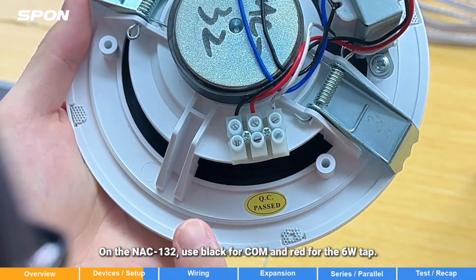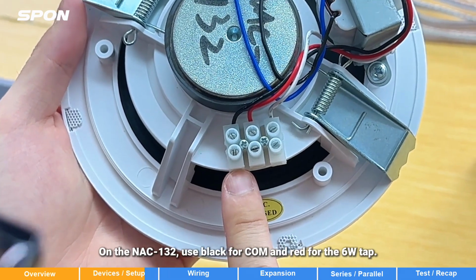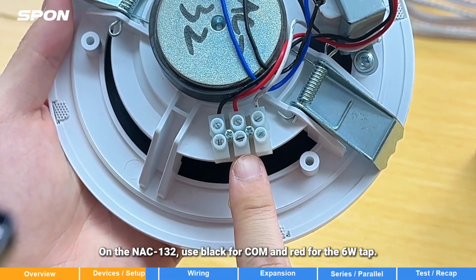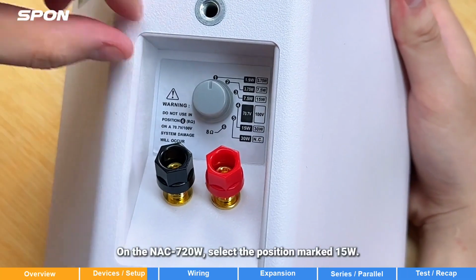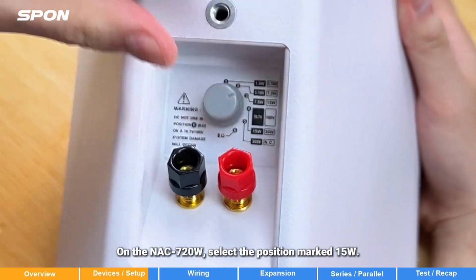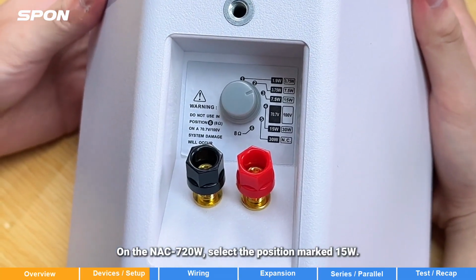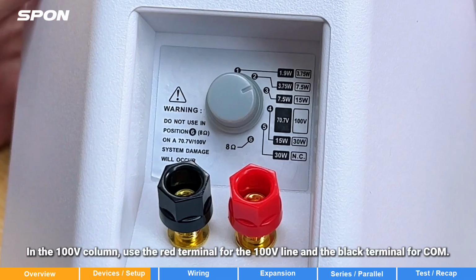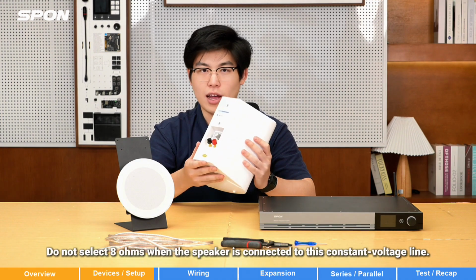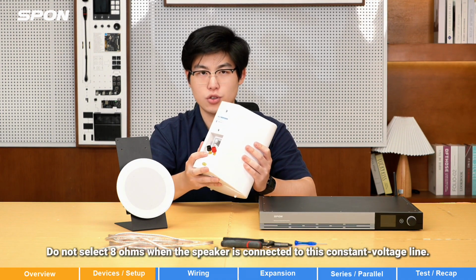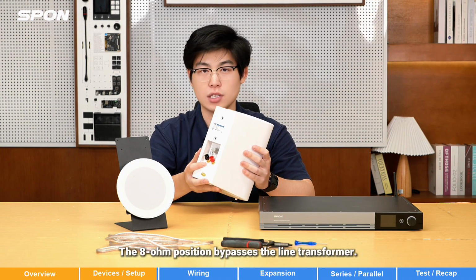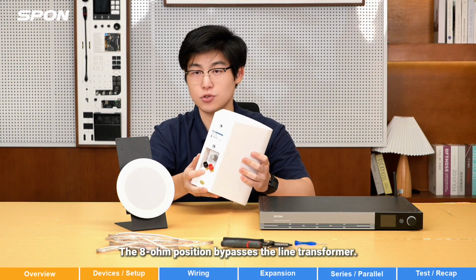On the NAC-132, use black COM and the red for the 6W tap. On the NAC-720W, select the position marked 15 watt in the 100 volt column. Use the red terminal for the 100V line and the black terminal for COM. Do not select 8 ohm when the speaker is connected to this constant voltage line. The 8 ohm position bypasses the line transformer.